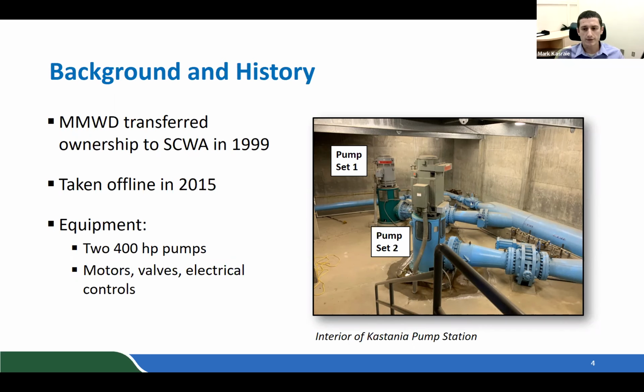The photo to the right shows two pump sets, pump number 1 and 2, the pump control valves, and of course the discharge piping. Currently, only pump set number 2 is anticipated to be operational, and we're aware that the motor for pump set number 1 requires refurbishment or replacement.